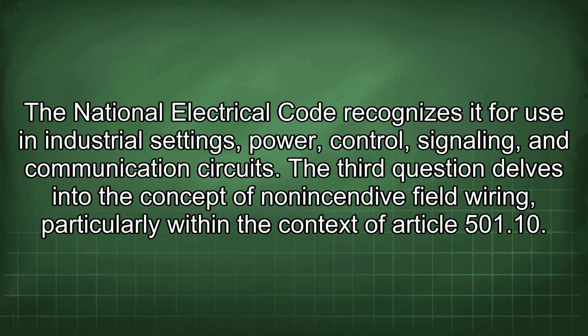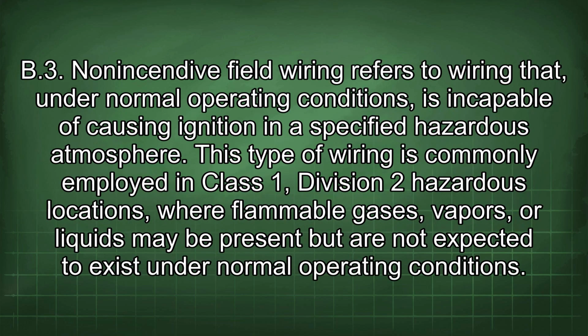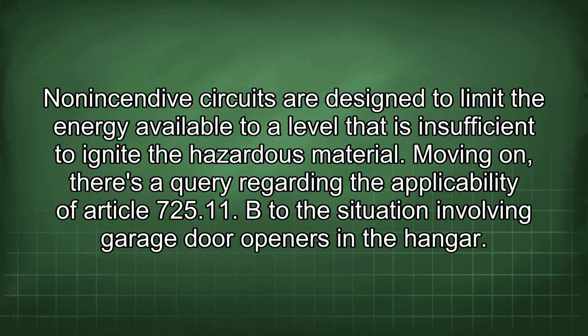The third question delves into the concept of nonincendive field wiring, particularly within the context of Article 501.10(B)(3). Nonincendive field wiring refers to wiring that, under normal operating conditions, is incapable of causing ignition in a specified hazardous atmosphere. This type of wiring is commonly employed in Class 1, Division 2 hazardous locations, where flammable gases, vapors, or liquids may be present but are not expected to exist under normal operating conditions. Nonincendive circuits are designed to limit the energy available to a level that is insufficient to ignite the hazardous material.